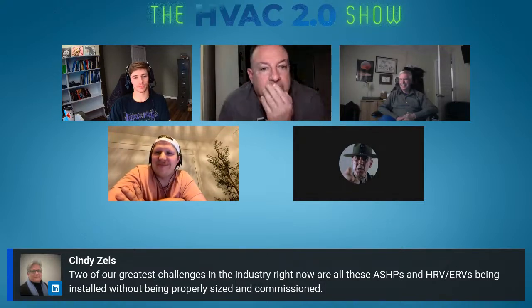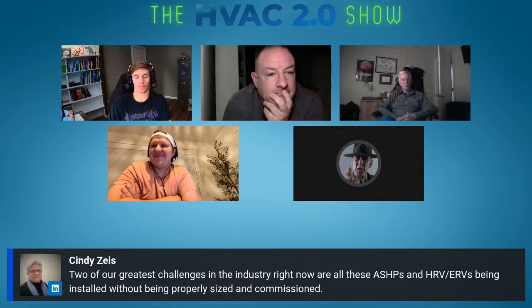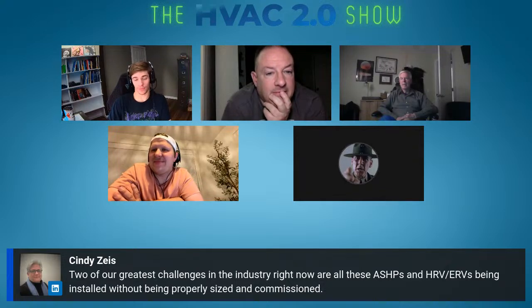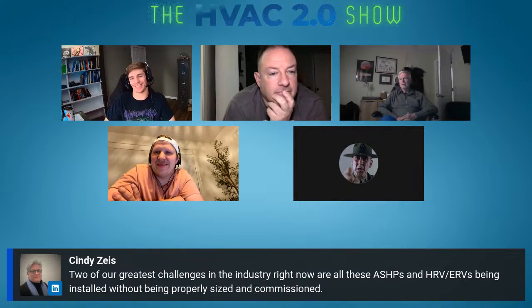Yes. Tanner, I was going to say I'm dealing with that situation right now, except they have a gas furnace instead of the heat pump, and they're blaming their spray foam. Oh, right. Yeah, that spray foam job's interesting, isn't it? They chose open cell though. They have an ERV. Is it balanced? Nope. Huh. Is there any dehumidifying going on? Nope. It's crazy the patterns you see when you pay attention. Have they been tracking the relative humidity?